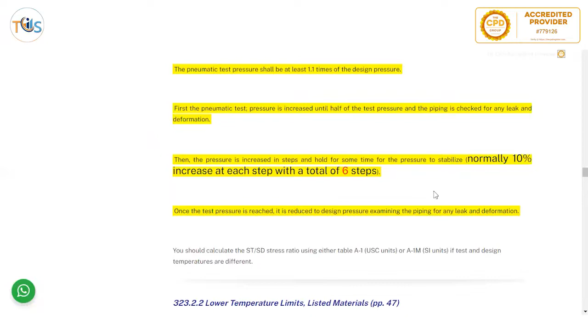Once the test pressure is reached, it's reduced to design pressure, examining the piping for any leak and deformation. So for both hydro and pneumatic test, once you reach that stage, according to procedure, they say, okay, wait for half an hour and look for leaks, so that the whole thing is stabilized. Then at the time when you are going to look for leaks or do some visual examination of the component, you have to reduce the pressure to the maximum allowable design pressure.